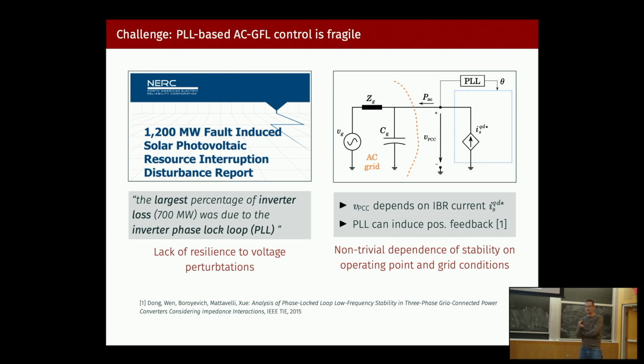There's also a more systematic reason for why these things go wrong. There's work on this, I don't want to go into too much detail, but you can look it up in this reference. At the end of the day, grid following control assumes that the AC voltage at the capacitor is not impacted by the power injection from the converter at all. But once the system is dominated by these converters, that voltage becomes a function of your power infeed, and you create a positive feedback loop, because you're controlling the power based off that voltage, which is fed back into the control to determine the power injection. So there's a tipping point where you have too many of these devices, or their rating gets too high, and things go wrong, becoming a positive feedback loop from a system level perspective.